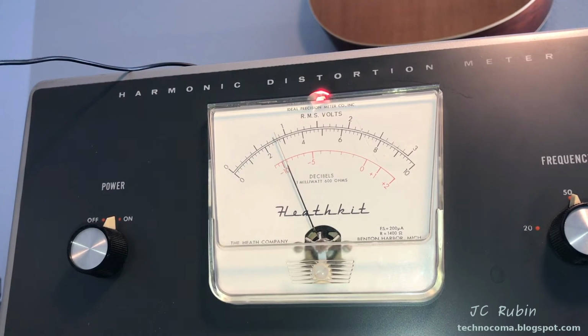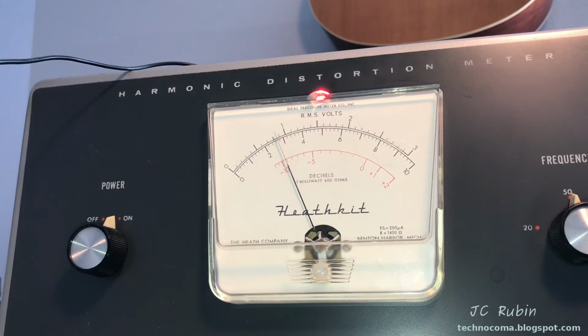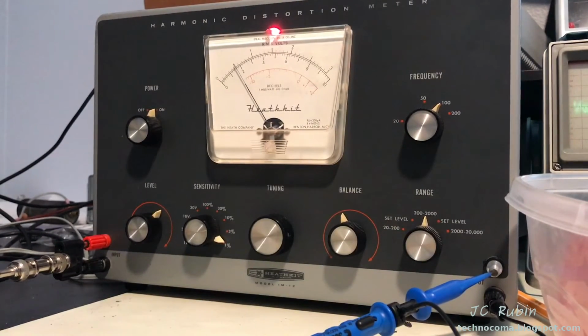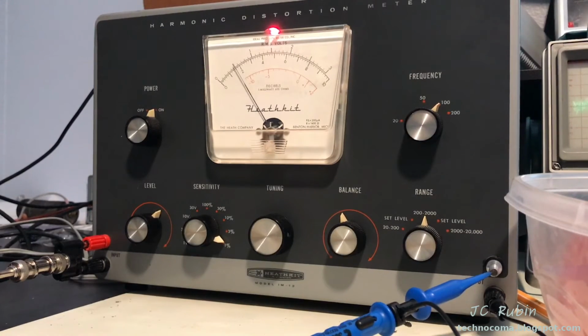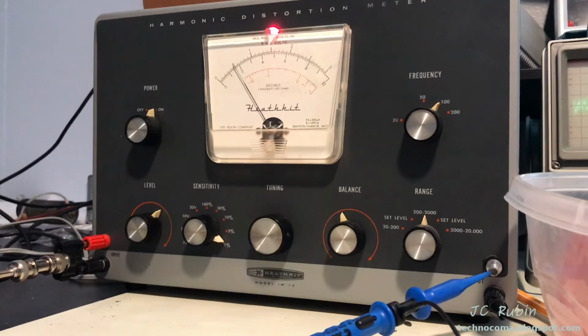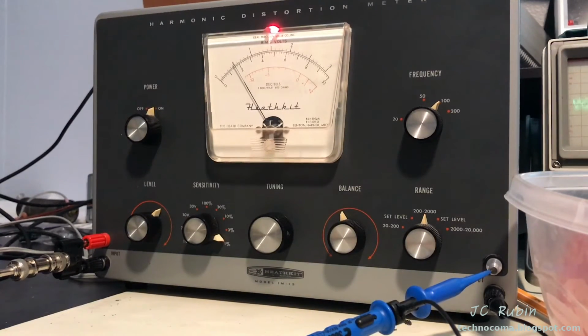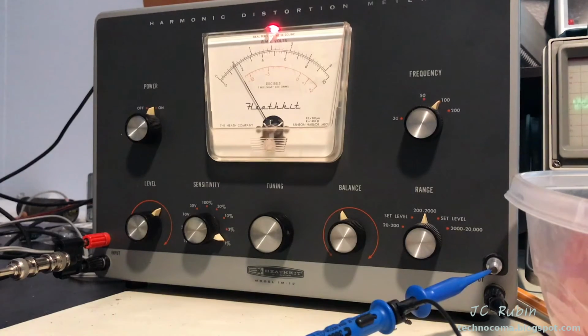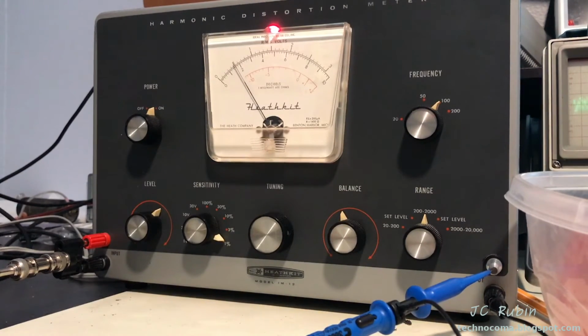I need to redo this calibration once more to get it back into specification with all of the other changes throughout this unit due to the voltage fluctuation from that capacitor swap out. I'm sure everything else will need to be calibrated as well, although I don't need to turn everything back to 0, everything just needs to be tweaked. The change that was made didn't have any overall effect on the characteristics of the machine. Here we're looking at a 1 kilohertz signal. This time it's 5 volts with a 50 ohm impedance that I've set up going into the unit. And I have tested this as a reference before and after, getting the exact same value of harmonic distortion.